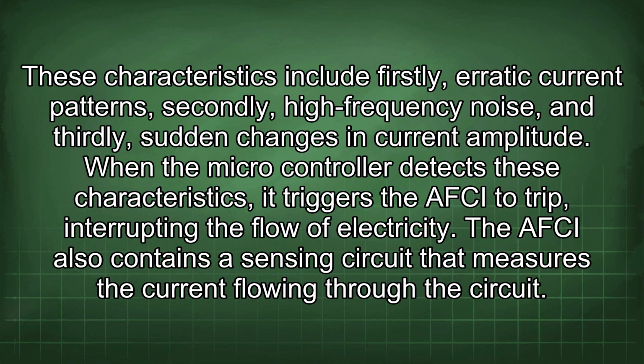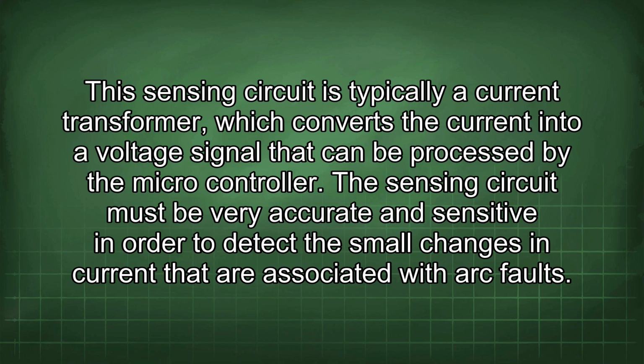The AFCI also contains a sensing circuit that measures the current flowing through the circuit. This sensing circuit is typically a current transformer, which converts the current into a voltage signal that can be processed by the microcontroller. The sensing circuit must be very accurate and sensitive in order to detect the small changes in current that are associated with arc faults.